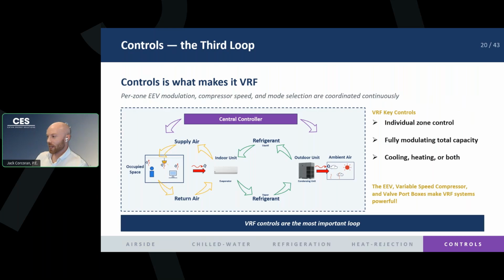And it also allows us to use that free cooling, right? We're going to get free cooling between zones. Our branch boxes are going to smartly send the hot refrigerant to the zones that need it, and it's going to smartly send our liquid and low pressure vapor to the zones that need it for cooling, right? And all that is not possible unless we have a very, very smart control system, which is why the control loop is extremely important in our VRF.